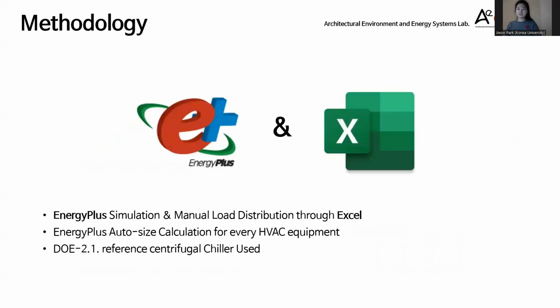This research utilized the building energy simulation software EnergyPlus, developed by the Department of Energy, to calculate the building's thermal load. Microsoft Excel was used to distribute the load to each chiller and calculate efficiency and energy consumption. For the chillers, the Department of Energy's reference chiller was assumed, and the efficiency, energy consumption, and other parameters based on PLR were calculated using the specific chiller's performance curve.